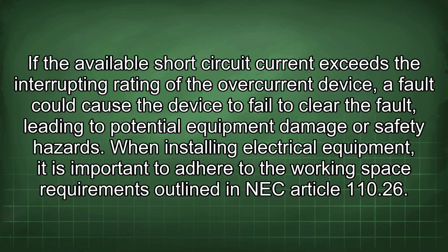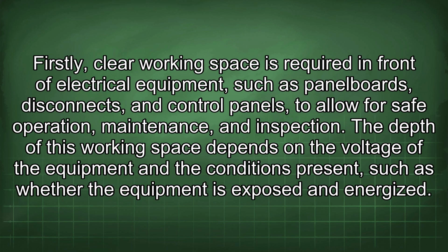When installing electrical equipment, it is important to adhere to the working space requirements outlined in NEC Article 110.26. Firstly, clear working space is required in front of electrical equipment, such as panel boards, disconnects, and control panels, to allow for safe operation, maintenance, and inspection. The depth of this working space depends on the voltage of the equipment and the conditions present, such as whether the equipment is exposed and energized.